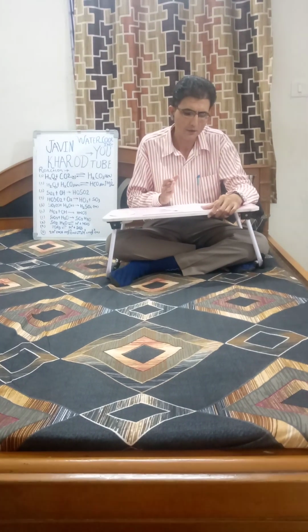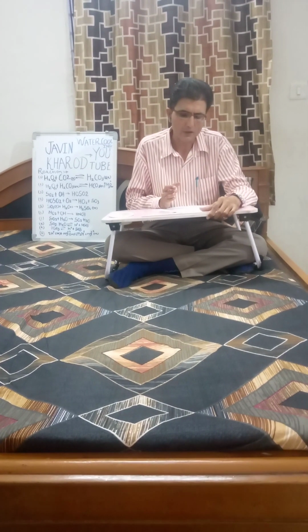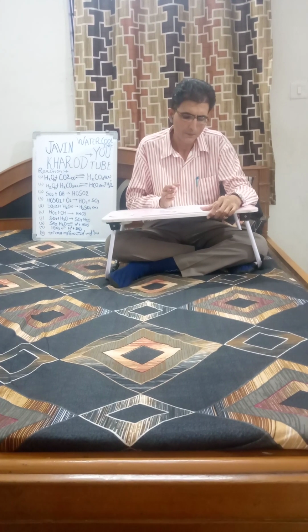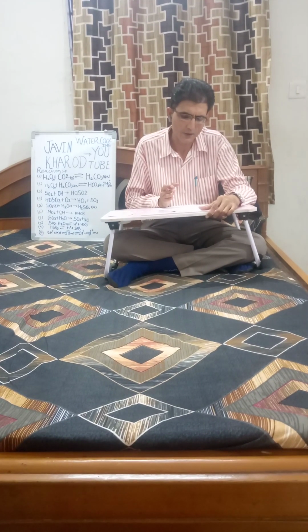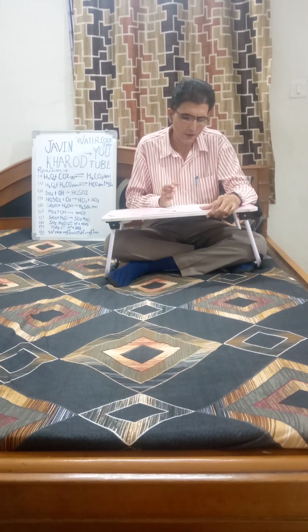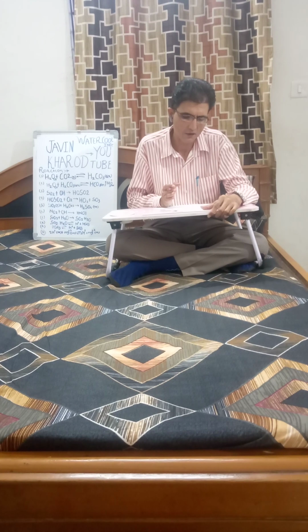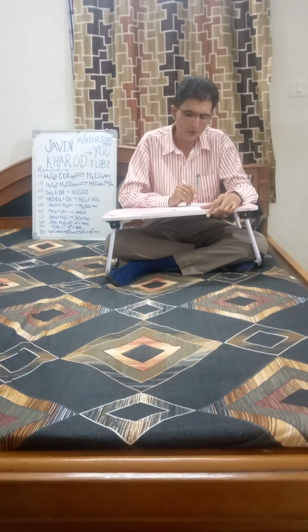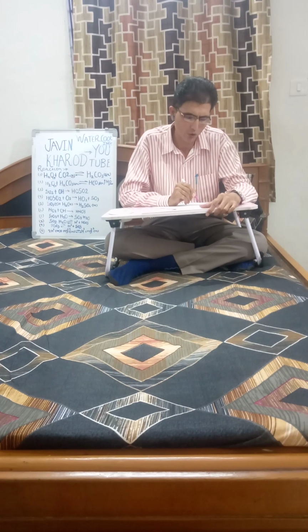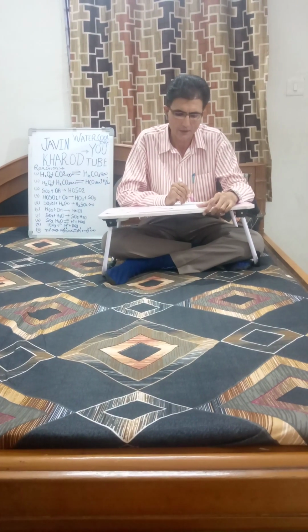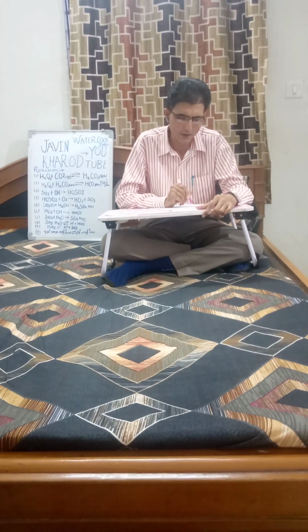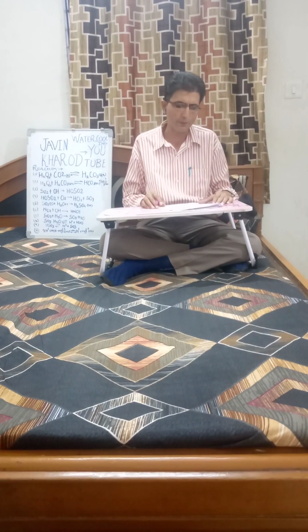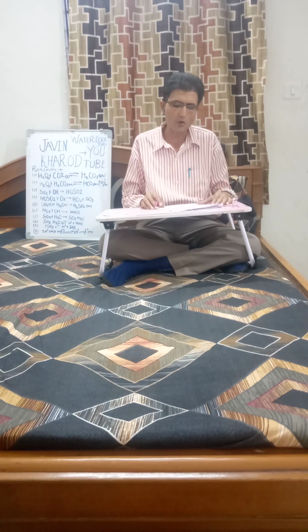Now, total dissolved solids, sometimes called filterable residue, is measured as the mass of residue remaining when a measured volume of filtered water is evaporated. Salinity is measured by water density or conductivity change caused by dissolved material. The probability of scale formation increases with total dissolved solids. Associated scale formers are calcium and magnesium carbonate and sulfate. Corrosion rate initially increases with salinity in response to increased electrical conductivity, but then decreases after reaching a peak at higher levels. Salinity decreases dissolved oxygen level.